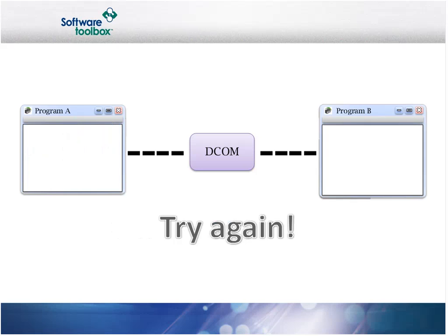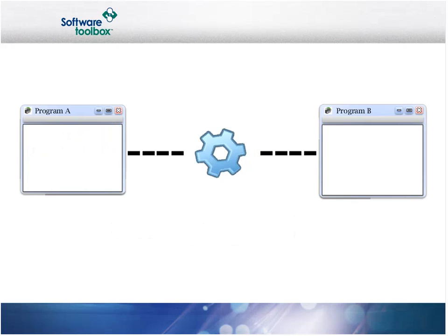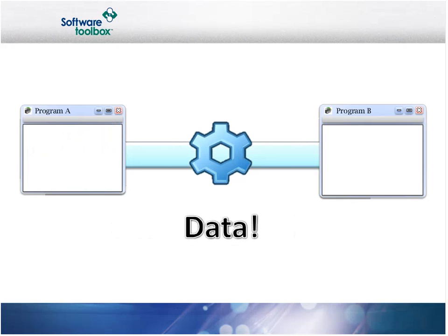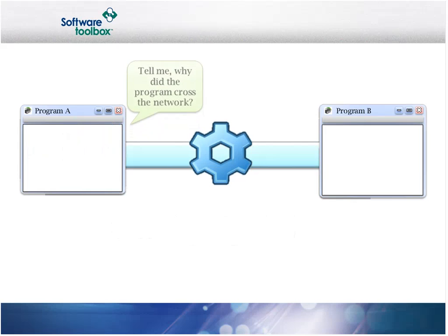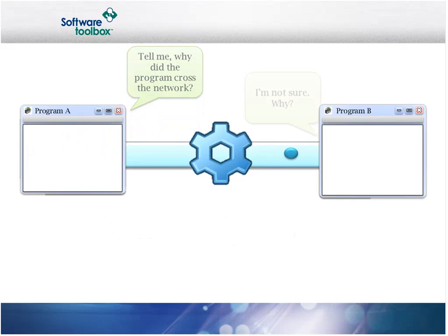But the data hub gets around all of this by tunneling data, not function calls. It's a big difference. The tunnel is optimized and designed to move data, and all communication is done asynchronously with non-blocking calls, so it can run significantly faster, actually up to 50 times faster in some cases, than an OPC tunnel that just passes OPC function calls up and down a TCP IP pipe.